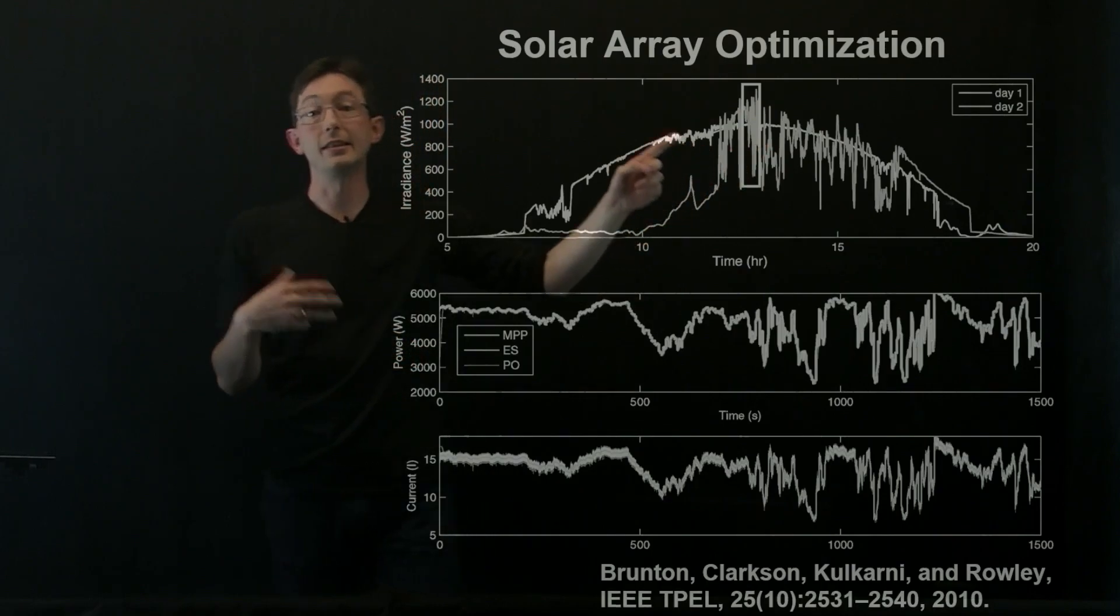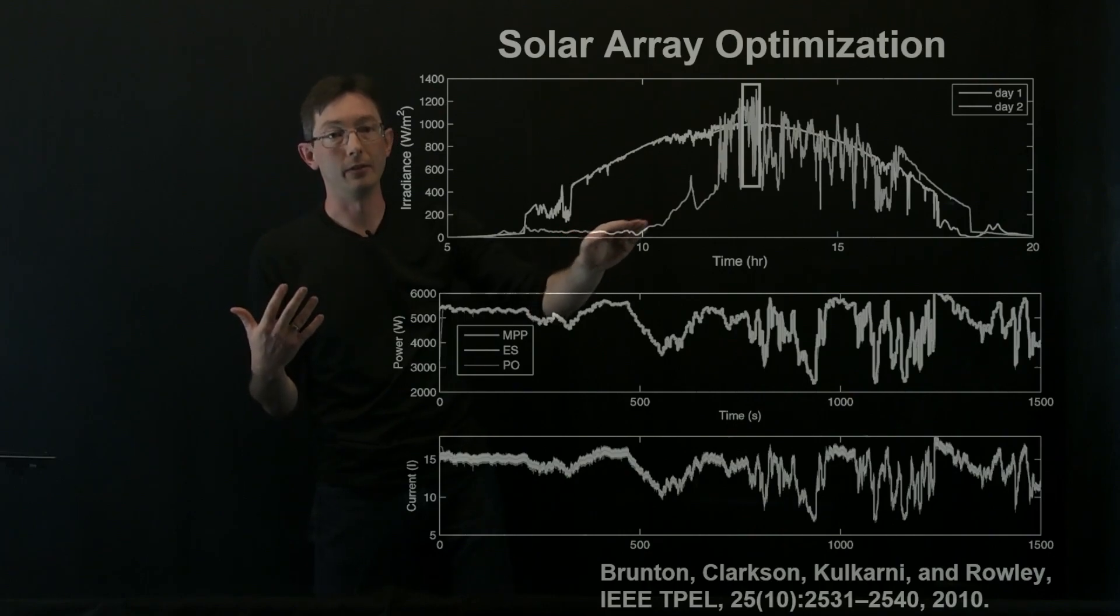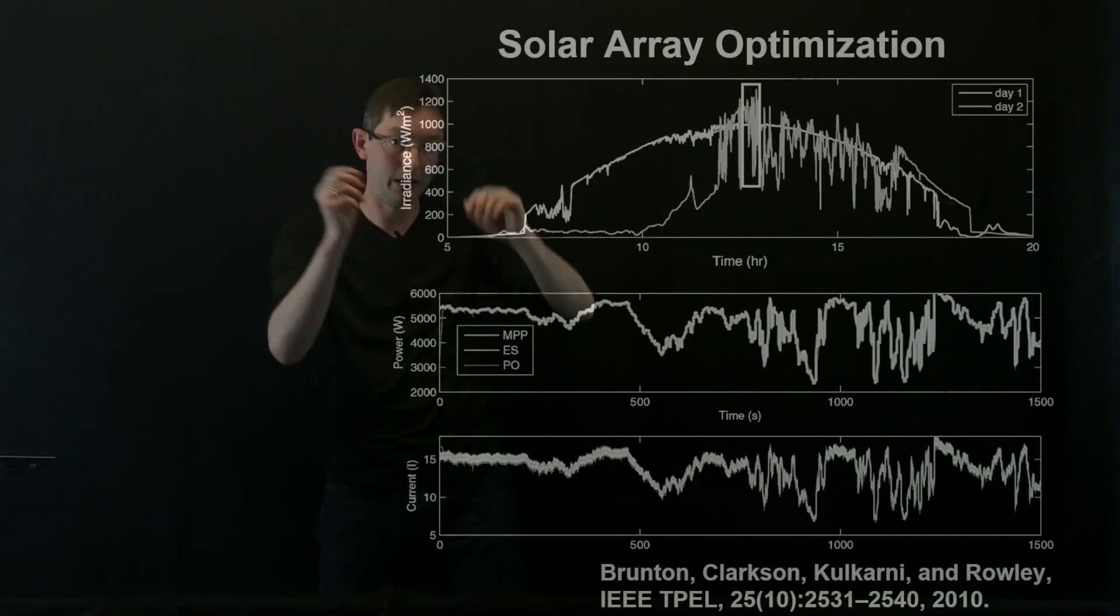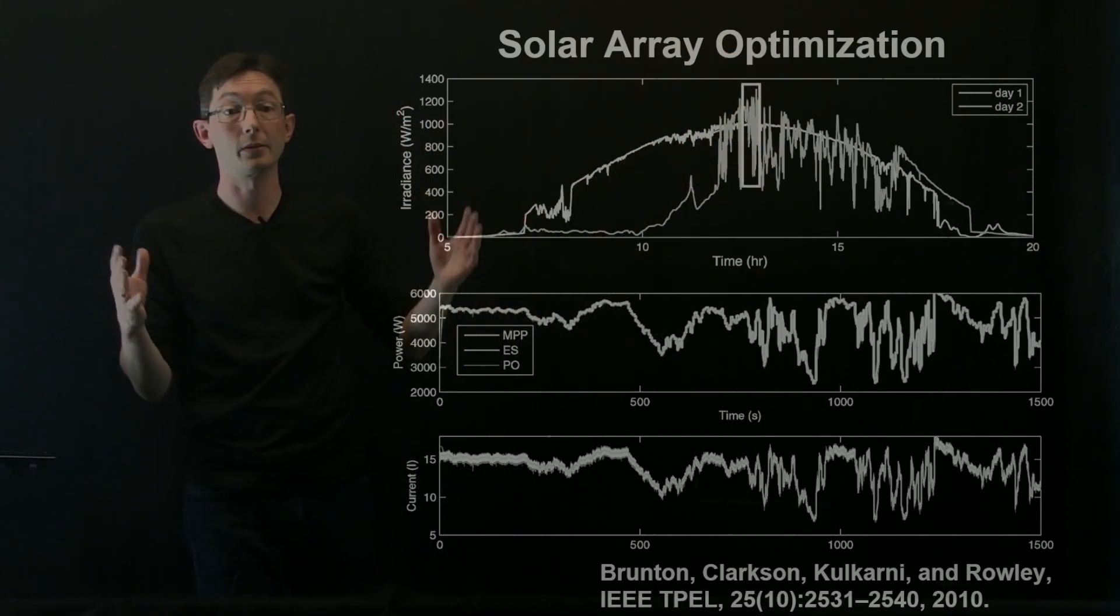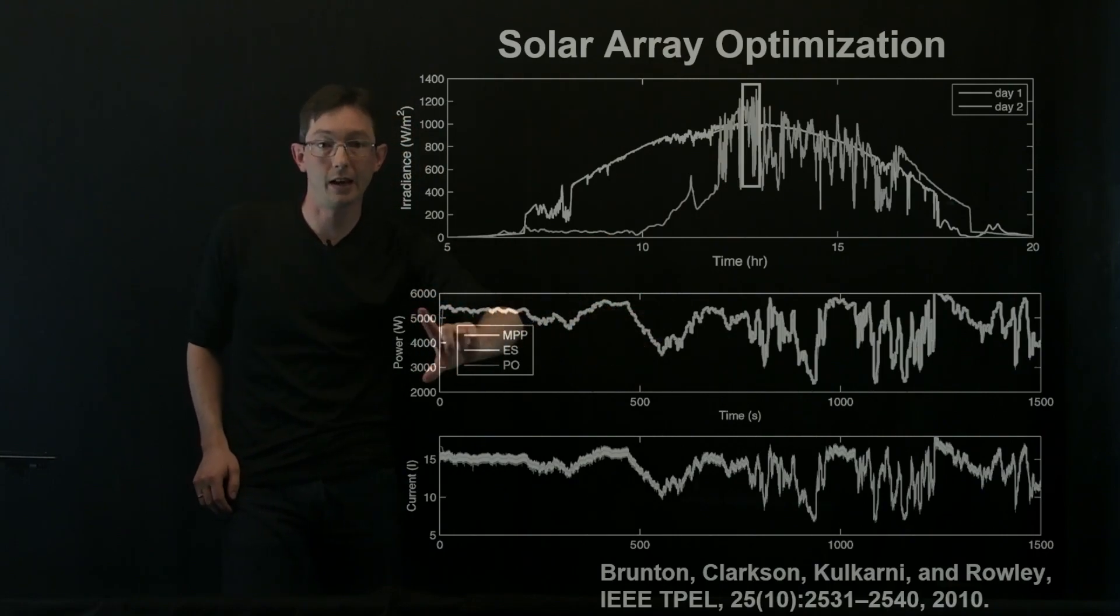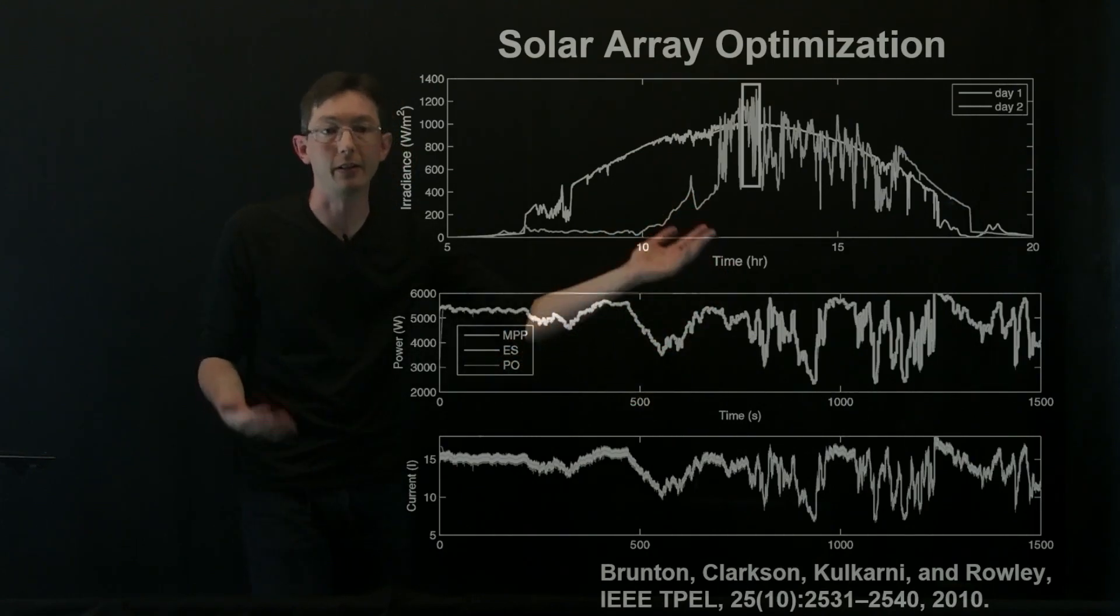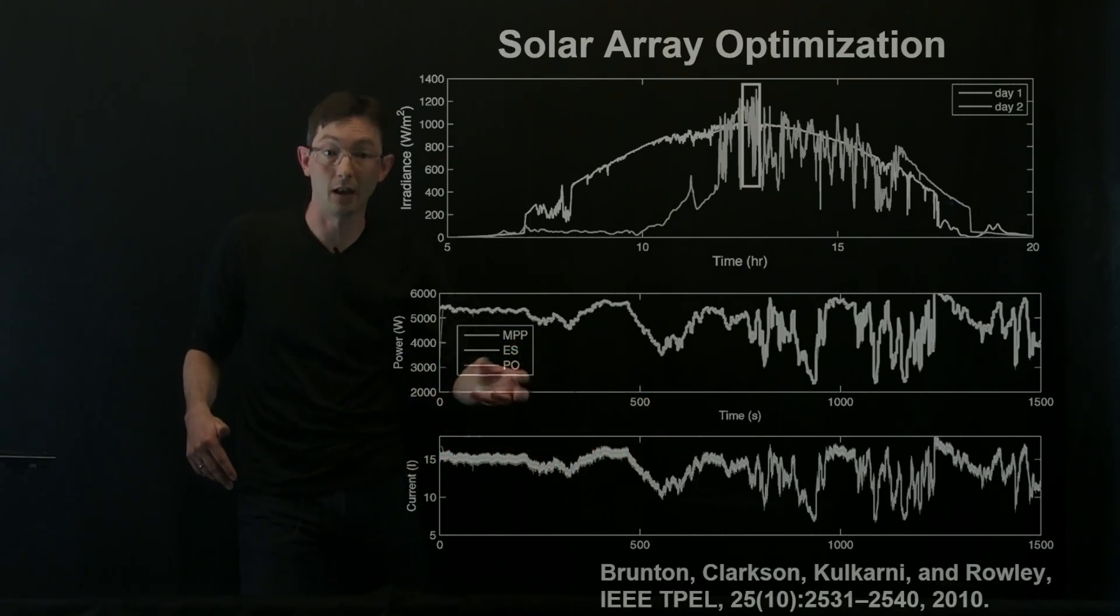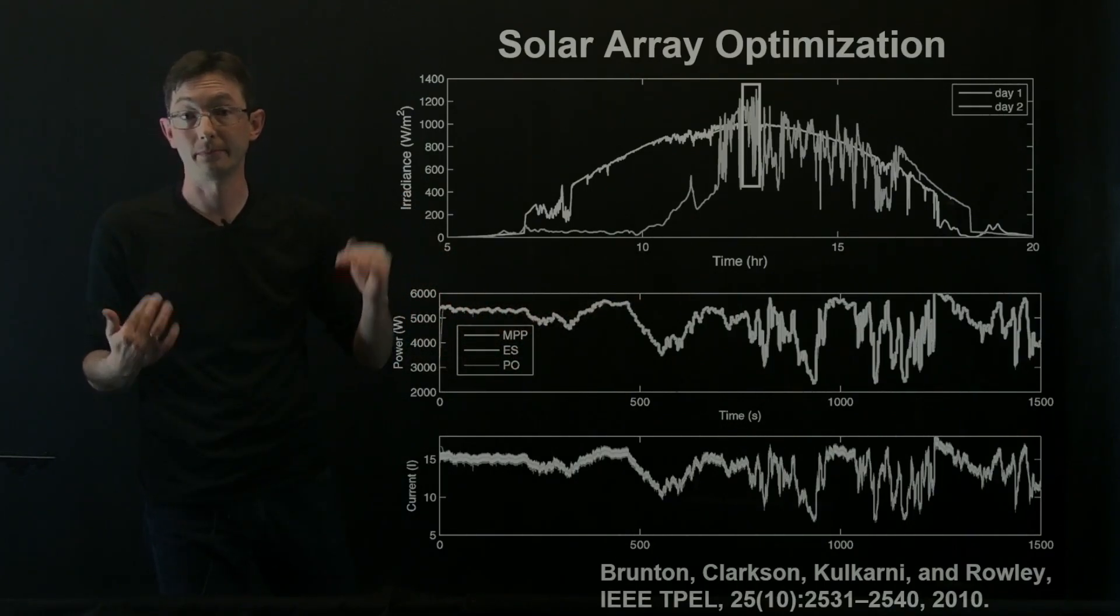But then on day two, you can see this is an example of real New Jersey weather. In day two, there's cloud cover. The cloud cover breaks sporadically and you get lots of sunlight. Then the clouds roll over, you get lots less sunlight. And this is very highly variable over the course of minutes or seconds. So I'm zooming into this little box here on day two, and you can see the power output is wildly swinging over the course of just a matter of minutes or hours. And this is the optimizing current, the control current that we have to continuously adjust to maintain the maximum power condition.